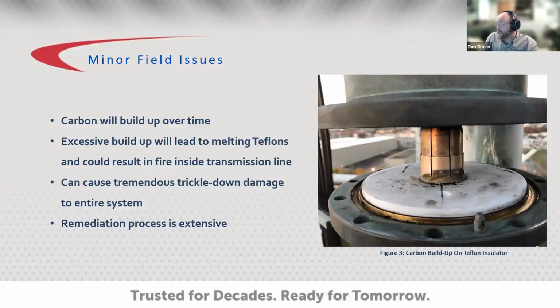The remediation process for this buildup of soot and carbon material consists of breaking each joint, which is rather time consuming, particularly in the Midwestern states where we have 1,500, 2,000 foot towers with a tremendous number of flange joints. So breaking each joint, sweeping off the debris, cleaning the Teflon with denatured alcohol, and then reconnecting the flanges prior to testing the overall system again. And this process will need to take place throughout the entire transmission line run.